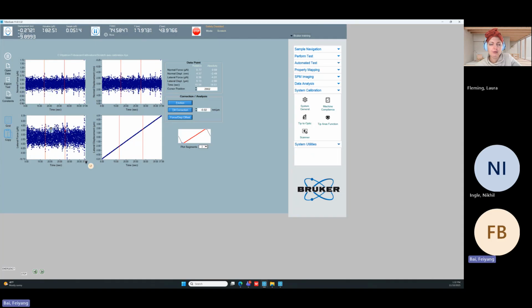You said the lateral force, as long as it's limited to 10 micronewtons, should be good, right? Yeah, that's a rule of thumb. What I'm looking for is that there's no weird big spike. There's one little spike at the end there, but I'm looking for a sustained long spike or just a lot of noise. Yours is very constant. I think that is just the noise level of your instrument, so roughly 10 micronewtons peak to peak. Okay.